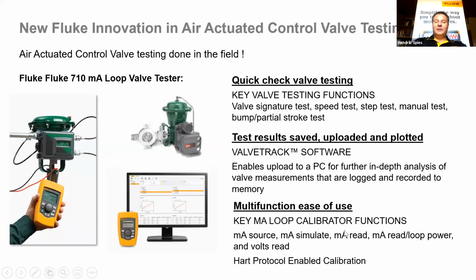On the multifunction, this is also a milliamp loop calibrator, which can do sourcing, simulation, reading of the actual milliamp value, and then we can do loop power as well, and some voltage as well. But what's nice about this unit is it has HART protocol enabled, so all the testing that we've indicated here can be done by connecting onto these valves via the HART protocol, and then it's an automated test. You just select the test, and the test is done.